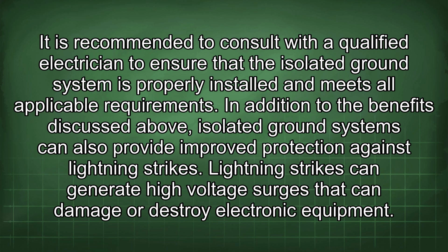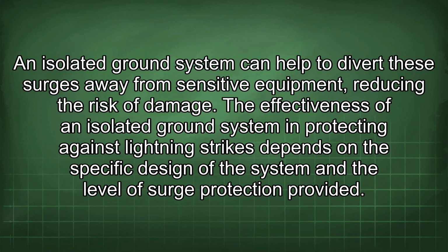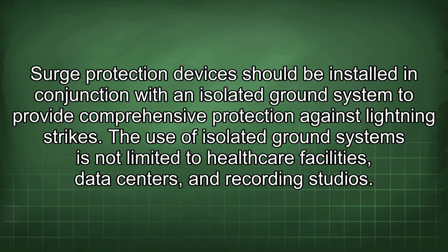meets all applicable requirements. In addition to the benefits discussed above, isolated ground systems can also provide improved protection against lightning strikes. Lightning strikes can generate high voltage surges that can damage or destroy electronic equipment. An isolated ground system can help to divert these surges away from sensitive equipment, reducing the risk of damage. The effectiveness of an isolated ground system in protecting against lightning strikes depends on the specific design of the system and the level of surge protection provided. Surge protection devices should be installed in conjunction with an isolated ground system to provide comprehensive protection against lightning strikes.